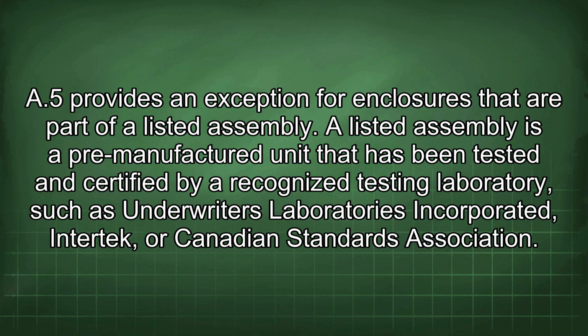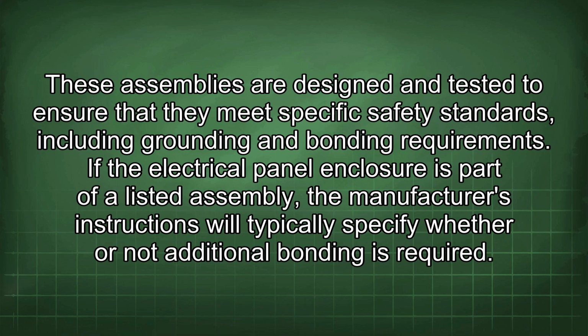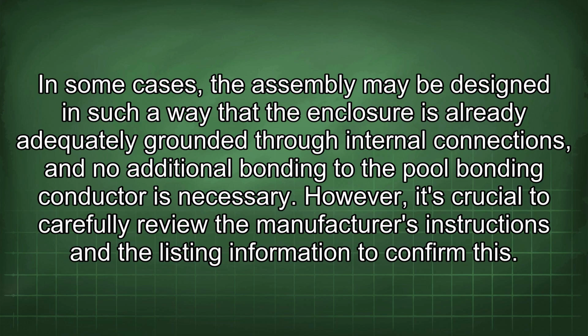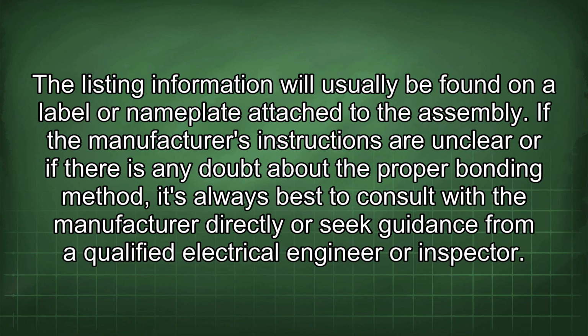A listed assembly is a pre-manufactured unit that has been tested and certified by a recognized testing laboratory, such as Underwriters Laboratories Incorporated, Intertek, or Canadian Standards Association. These assemblies are designed and tested to ensure that they meet specific safety standards, including grounding and bonding requirements. If the electrical panel enclosure is part of a listed assembly, the manufacturer's instructions will typically specify whether or not additional bonding is required. In some cases, the assembly may be designed in such a way that the enclosure is already adequately grounded through internal connections, and no additional bonding to the pool bonding conductor is necessary. However, it's crucial to carefully review the manufacturer's instructions and their listing information to confirm this. The listing information will usually be found on a label or nameplate attached to the assembly.